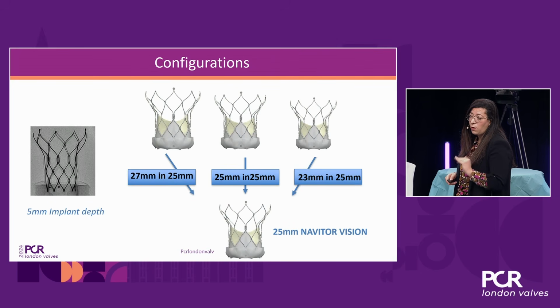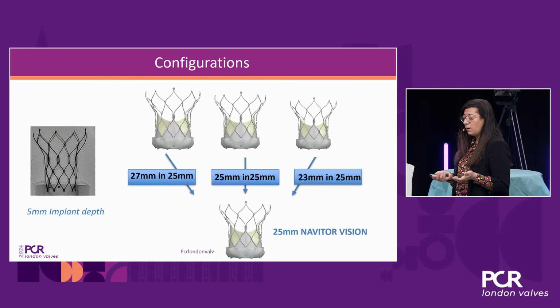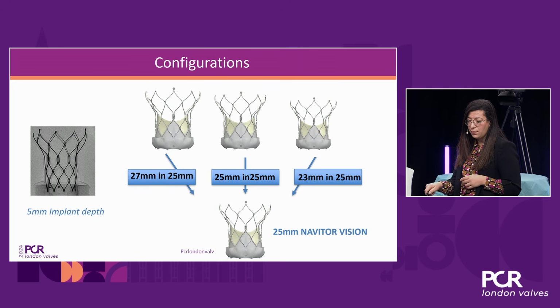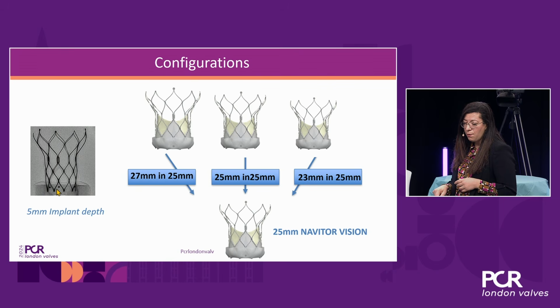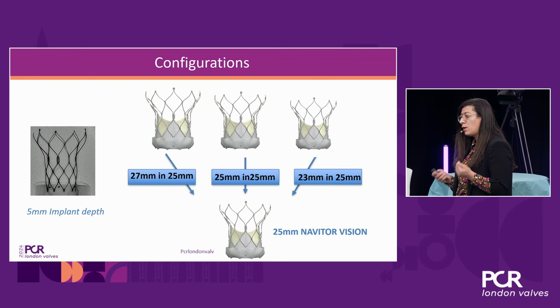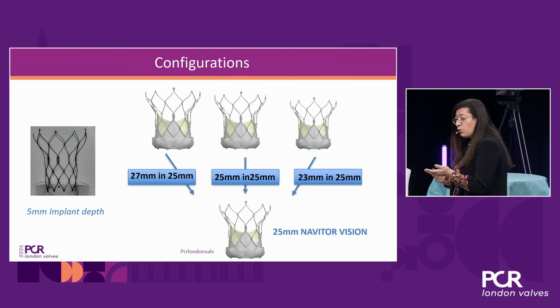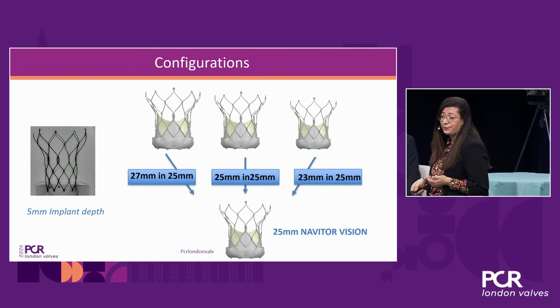So we've been testing 3 configurations. Let's say that we have a degenerated 25 millimeter Navitor Vision. You see here that we implant with the markers. This is the holder simulating the annulus, and the markers show that above them we had a 5 millimeter implant depth. We're going to put another Navitor inside and see what happens. One of the key points, as I said, is valve expansion, so we're going to see which sizing is the best. If we put a 27 into 25, what will it give us? 25 in 25, as well as 23 in 25.